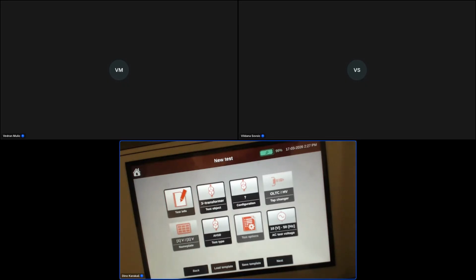We can save this template if we want, but we will save the later version of test settings, because when we select winding resistance measurement, it's kind of more complicated. So this is the test ready menu. This is only for automatic vector group detection. And now we start the test. Device runs the test. Here in this white field, I hope you can see the device running testing all of the groups. And when the result is ready, you will see the configuration in this white field.